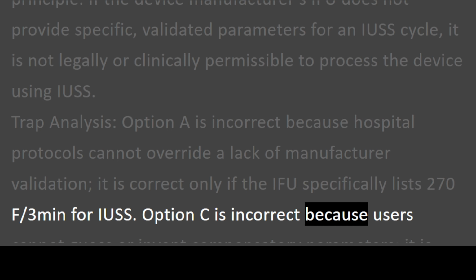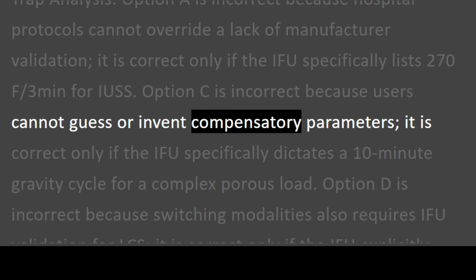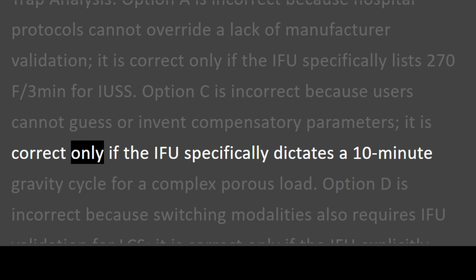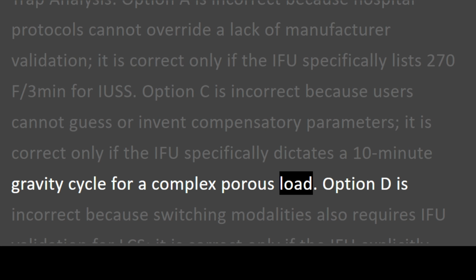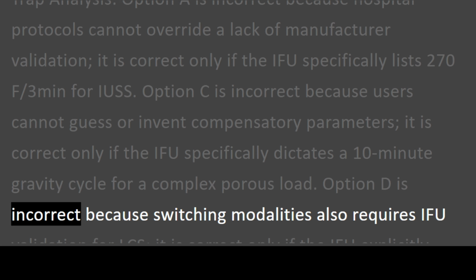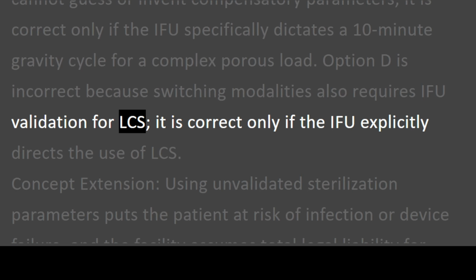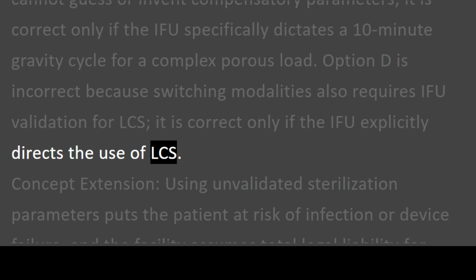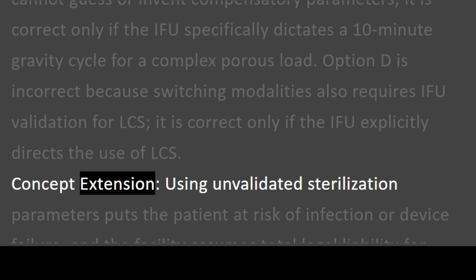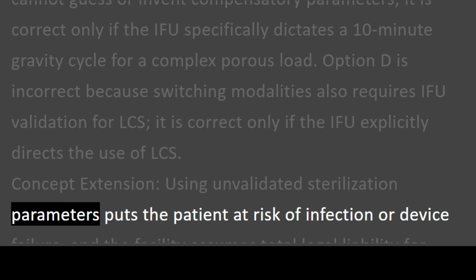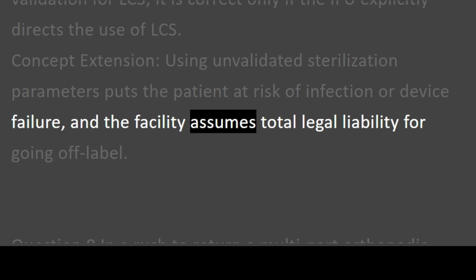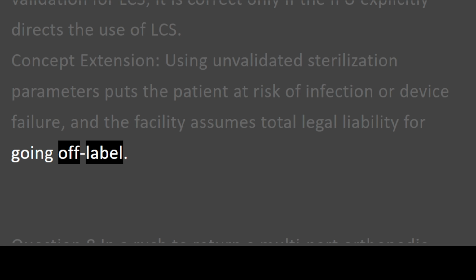Option C is incorrect because users cannot guess or invent compensatory parameters. It is correct only if the IFU specifically dictates a 10-minute gravity cycle for a complex porous load. Option D is incorrect because switching modalities also requires IFU validation for LCS. It is correct only if the IFU explicitly directs the use of LCS. Concept extension. Using unvalidated sterilization parameters puts the patient at risk of infection or device failure, and the facility assumes total legal liability for going off-label.